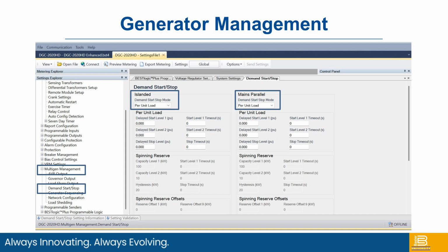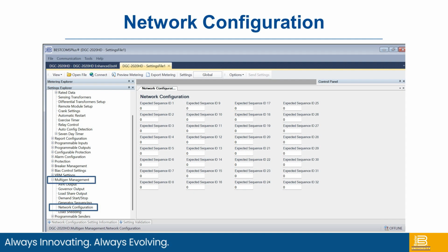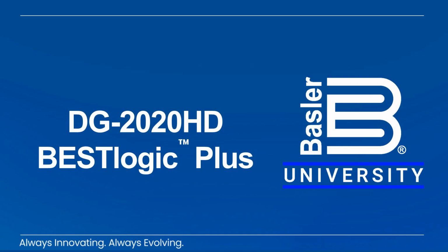Generator management. As I had mentioned earlier, this is where you come in and tell the unit what type of system it is in and what type of breakers and generators it's controlling. As you can see, I've got a couple of things highlighted here, like if it's an island or if it's in mains parallel. Network configuration. This is how the DGCs will talk to each other in multiple gen applications and setting up network configurations.